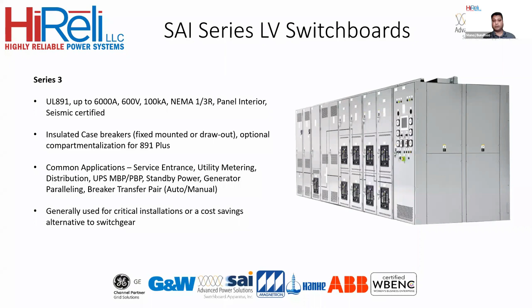Next slide. So the low voltage switchgear, as you can see, goes up to 10,000 amps. They use insulated case circuit breakers only, and they are draw out. So this is a compartmentalized option, whereas the other one is not really compartmentalized. It's like comparing, in medium voltage, metal enclosed to metal clad. This is the metal clad version of the low voltage switchgear. Again, similar applications, and also used in critical installations where safety and reliability are key elements.